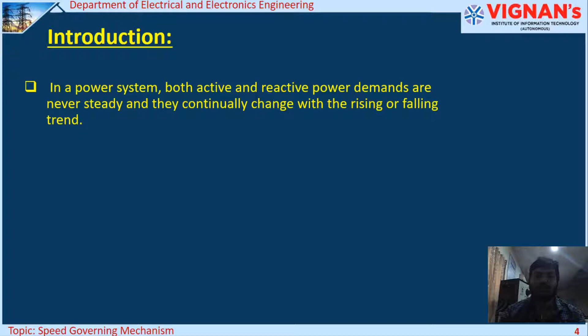Basically, in a power system, there is both active and reactive power demand, which will continuously change due to the rising and falling load demand, and it is essential to balance the power that is supplied and the power that is demanded, to maintain the frequency and the voltage constant. The input to the steam turbo generators is steam input, and for the hydro generators is water input. It must be continuously regulated to match the active power demand, failing which the machine speed will fall and there will be a consequent change in the frequency, which is highly undesirable. So it is very important that we maintain the frequency constant throughout the operation of the system for its stable operation.